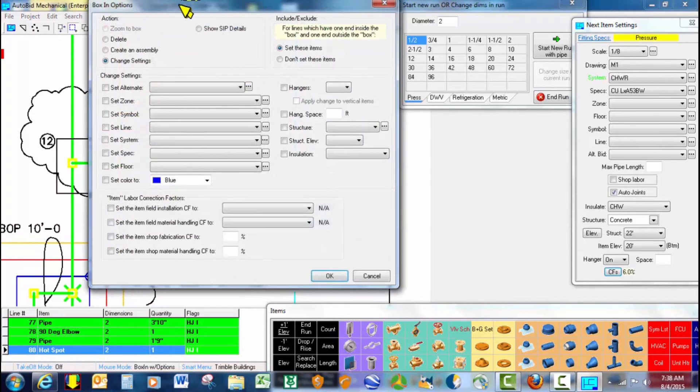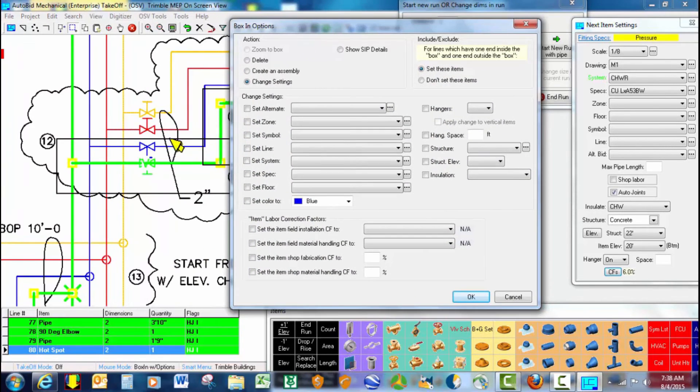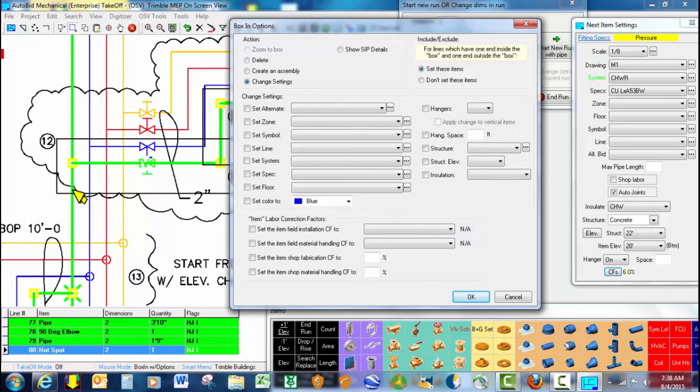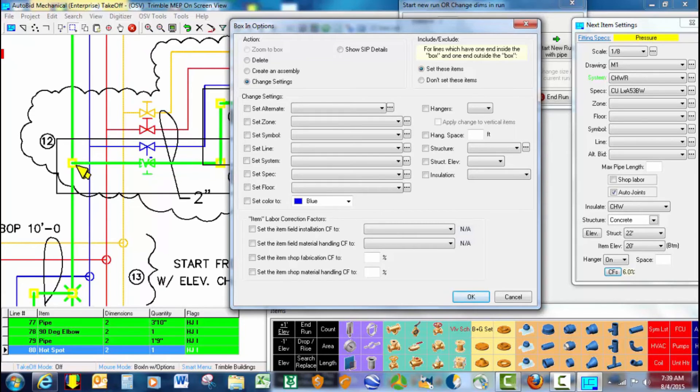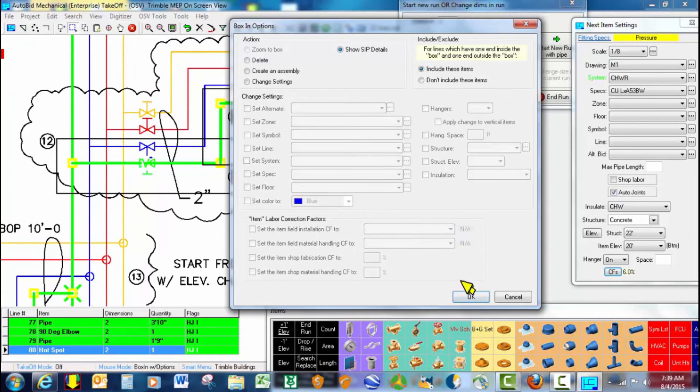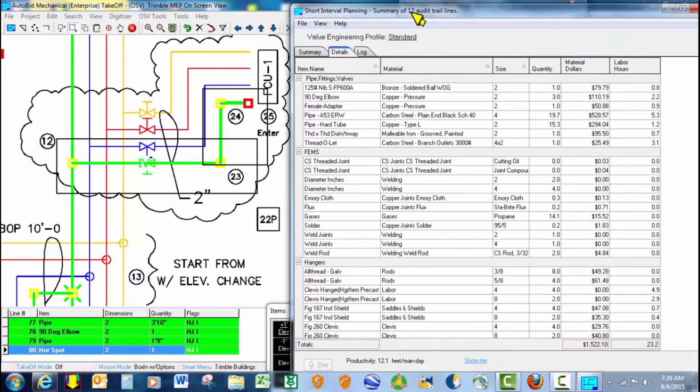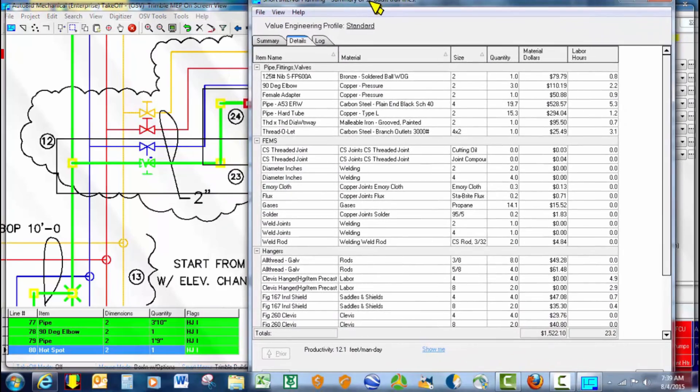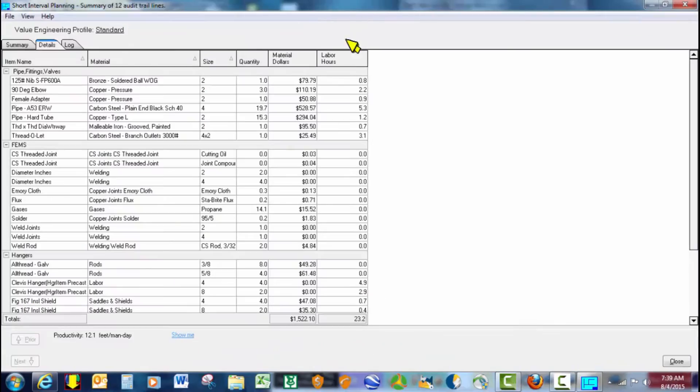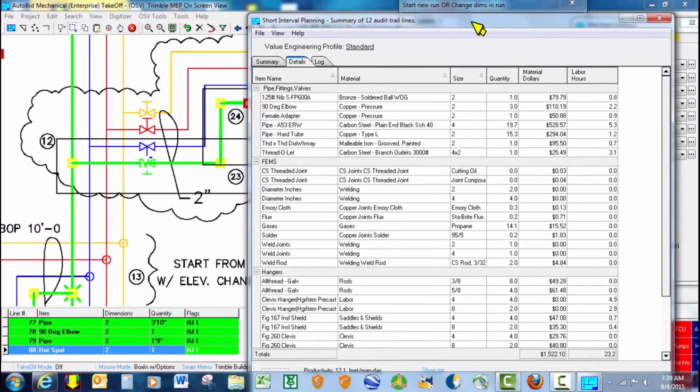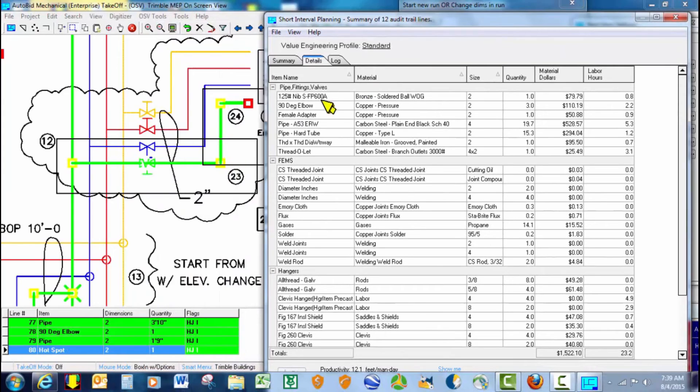So it tells us there's our ball valve at the very top, our soldered ball valve. We got the 2 inch copper elbow. We've got the actual connection, which would be a dielectric nipple that's attached into the Thread-O-Let, and then we would have a female adapter and the 2 inch 90 degree elbow.